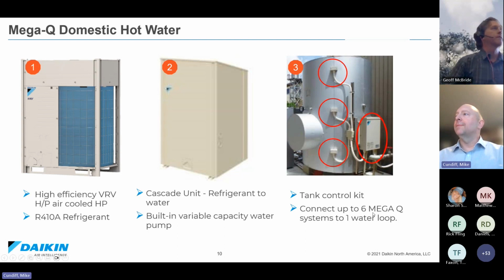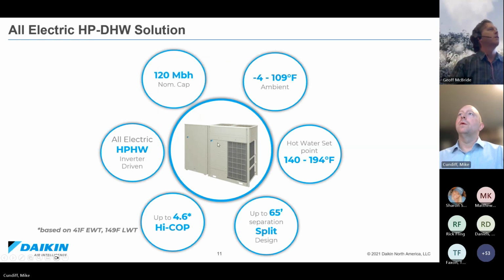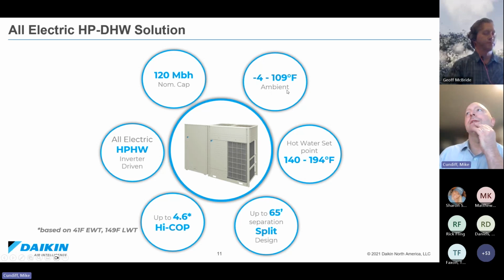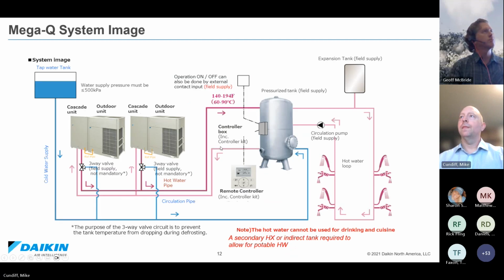You can connect up to 6 Mega Q systems to one water loop as well. So 120 MBH capacity, rated outdoor conditions, -4 to 109. Hot water set points of 140 to 194, up to 65 feet separation split on this. So you're pretty flexible in terms of where you put this. Up to 4.6 COP, and it is all electric for the electrification movement that we're all seeing out there.